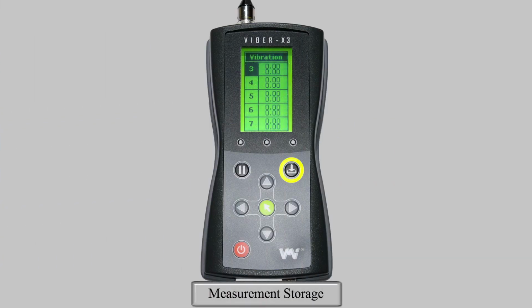You can store your measurements on the Viber-X3 by pressing the Save key, during vibration and temperature measurement, and during balancing. There are 100 storage slots each for vibration and temperature measurements, and 10 for balancing readings. When you save vibration measurements, the bearing condition measurement is also stored. When you press the Save key, you will gain access to the storage slots. Press the up and down arrows to move between individual slots, and the left and right to move 5 spaces at a time. When you have your measurement highlighted over the desired memory slot, press the green key. This will save the measurement. If you wish to exit the menu without saving, simply press the Save key again.